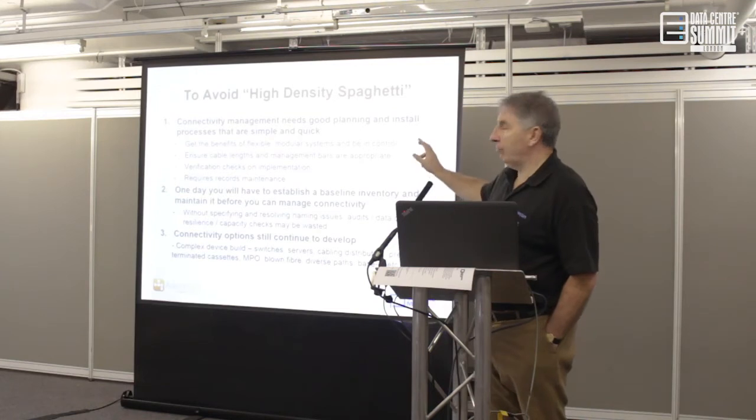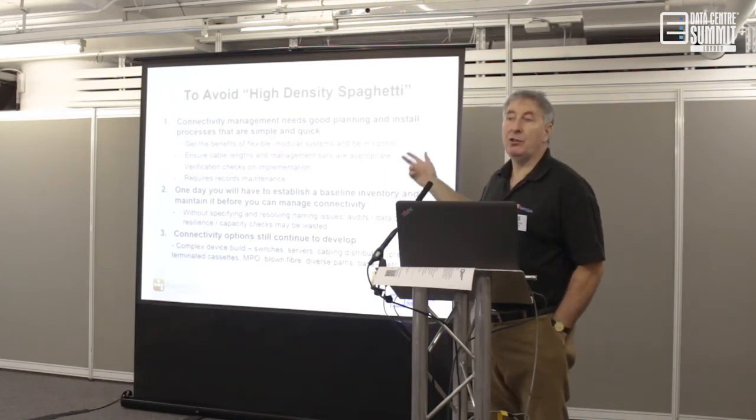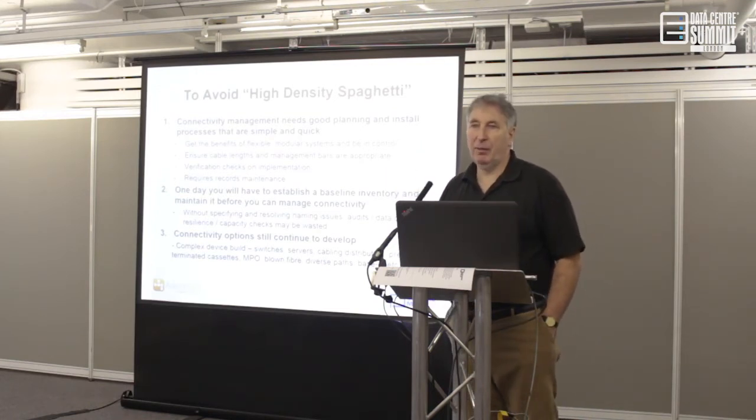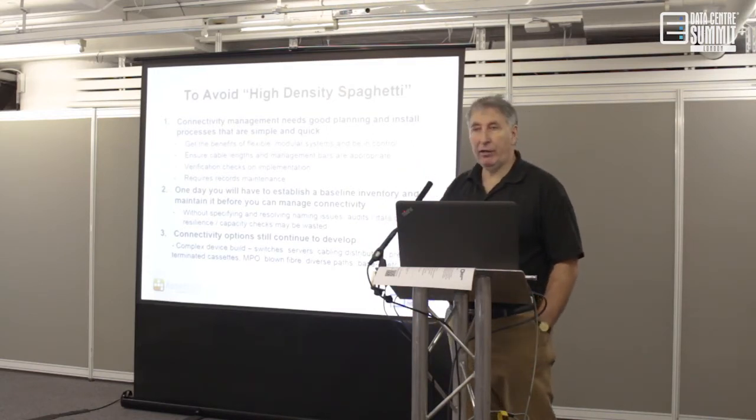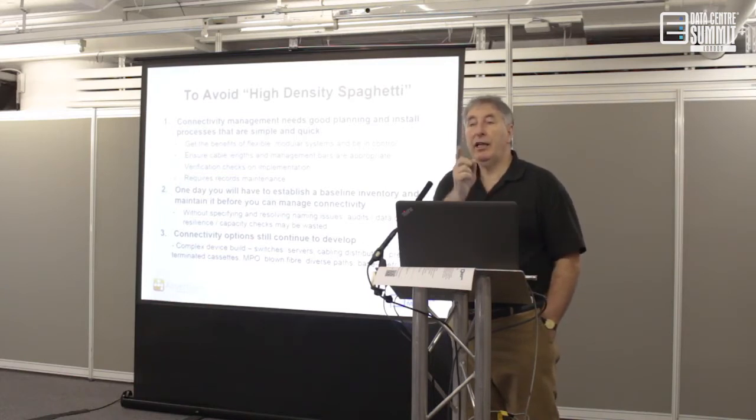But if you want to get the benefits of flexible modular systems, the great thing is you can change things so quickly. The bad thing is you can change things so quickly, none of your documentation keeps up to date with it. And you do need still to always go back and do verification checks. What we do within our audit system is we can pull out from our database, for this particular room in Singapore, what's changed in the last 4 months? Because when one of our guys goes there, he knows which racks to go to and say, just check the cable management because we've had some recent works there, done by a contractor.